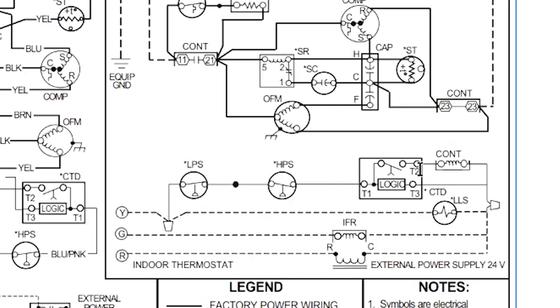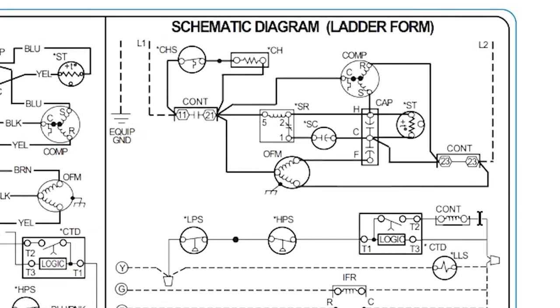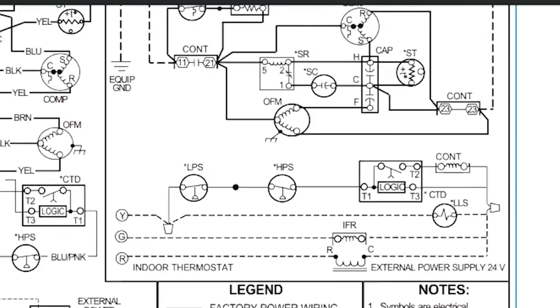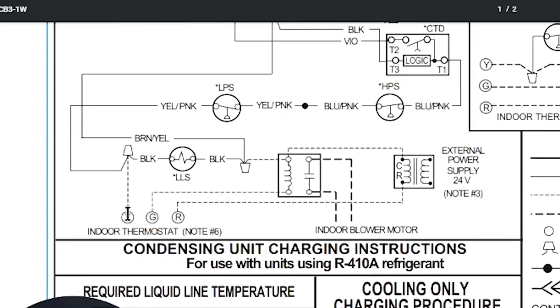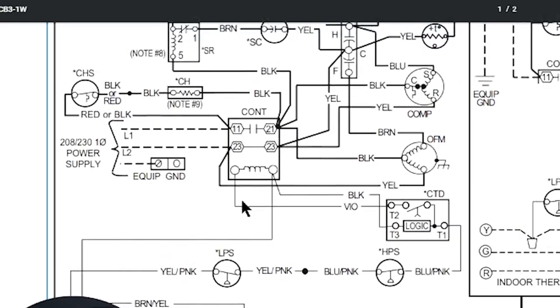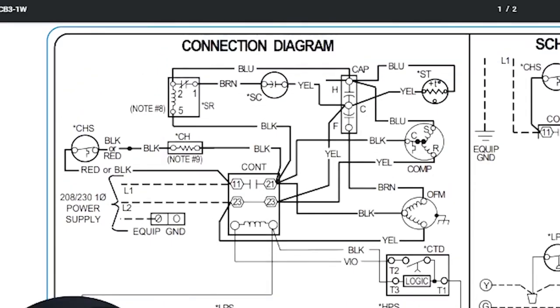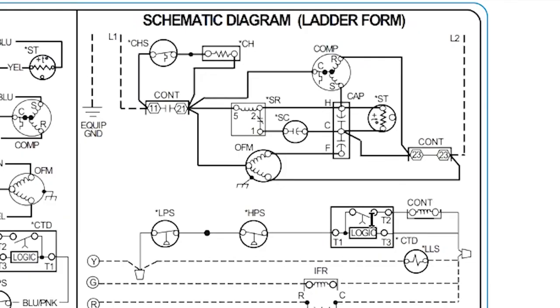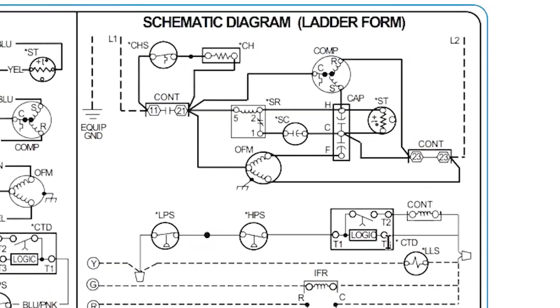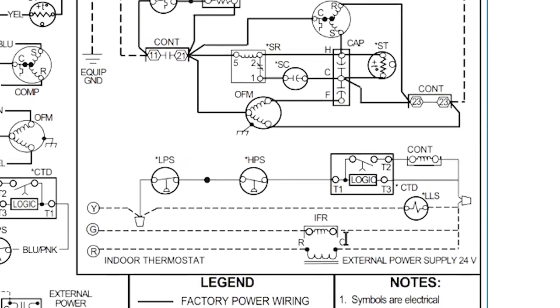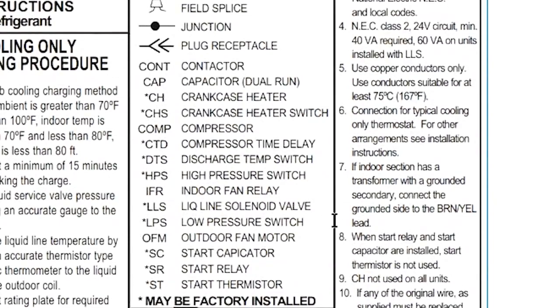After the pressure switches, we go through a logic gate and then make connection to the contactor coil, which energizes the contactor relay points. The Y wire comes up, goes through this symbol — an upside-down Y shape — which indicates a time delay. This is a compressor time delay (CTD): a small circuit board that creates the timer, allowing the compressor contactor to energize without short cycling. There's also a liquid line solenoid valve powered by Y.